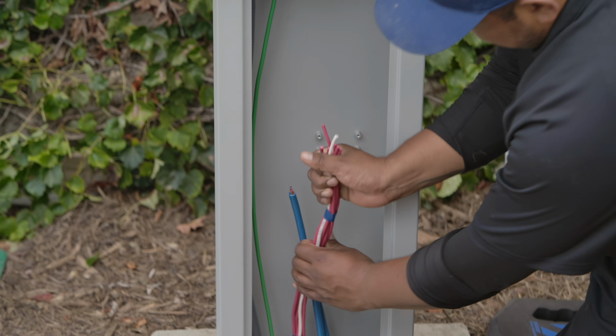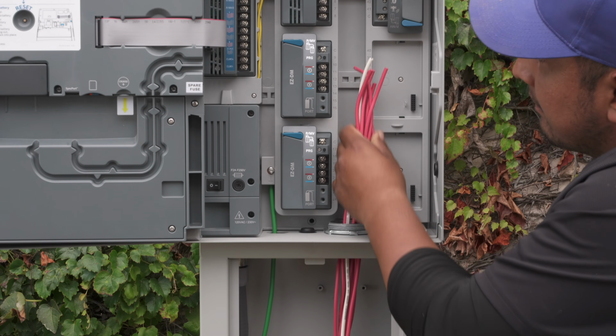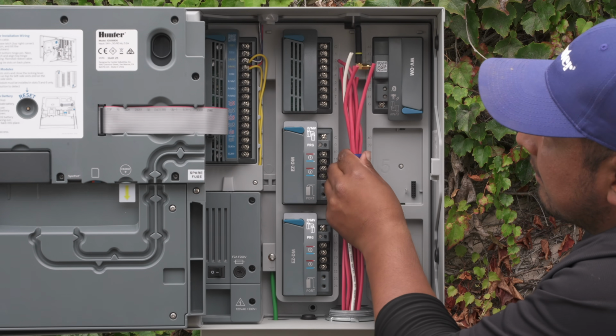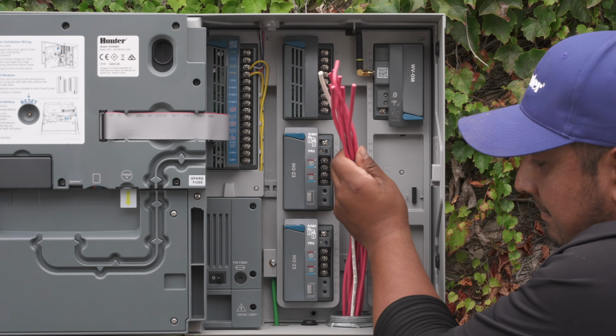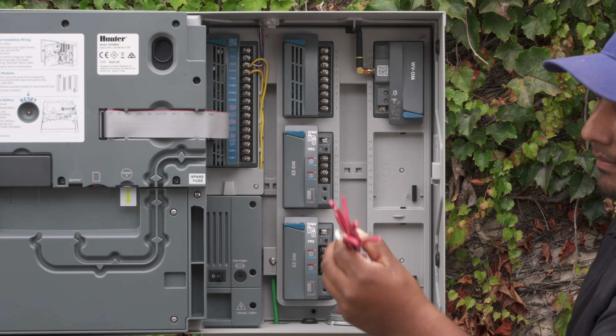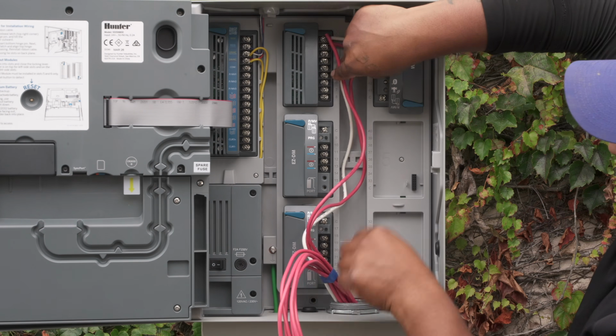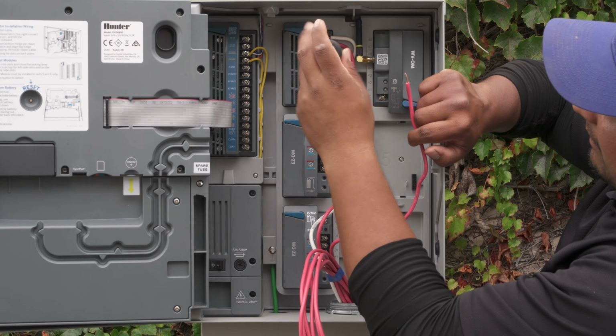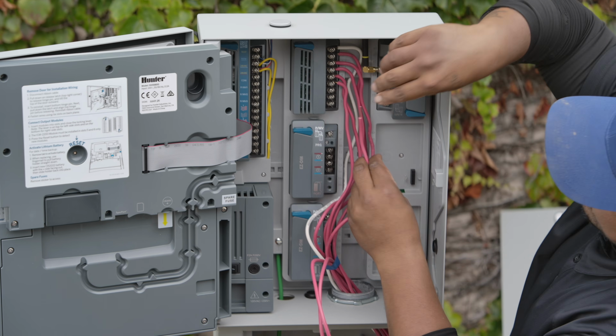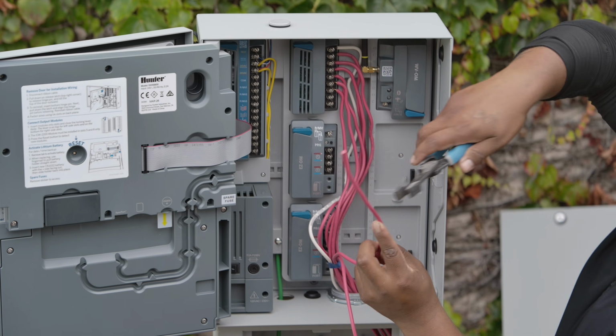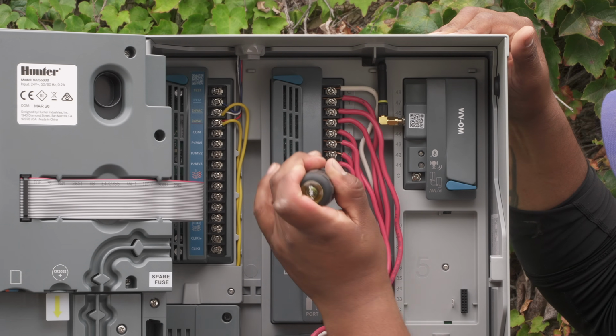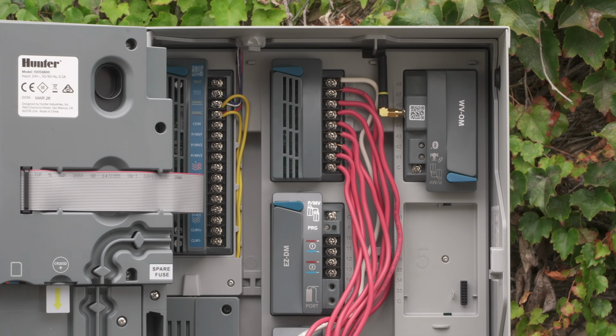Field wiring may consist of conventional wiring bundles or one or more 2-wire paths, depending on the controller output configuration. Install field wiring in its own conduits with a field wiring sweep. Connect field common wires to the COM terminal on each output module. Then connect the station output wires to the numbered terminals on each output module.